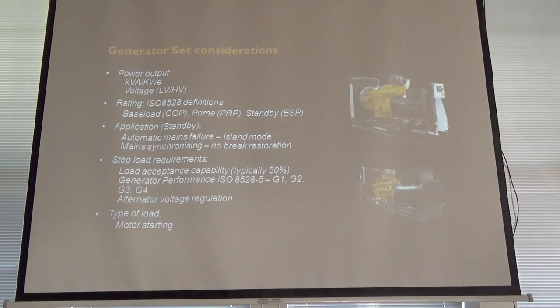So for instance, just picking a particular size of generator, a KTA 38 Cummins unit, KTA 38 G5 designation will give you 1100 kVA at standby rating, it'll give you 1 MVA at prime rating, and it'll give you 770 kVA at COP. Now these are the key things related to ISO 8528-1, and it's one of the most important things I say for customers and consultants to have a good understanding of, so that you can designate an appropriate rating for your generator.